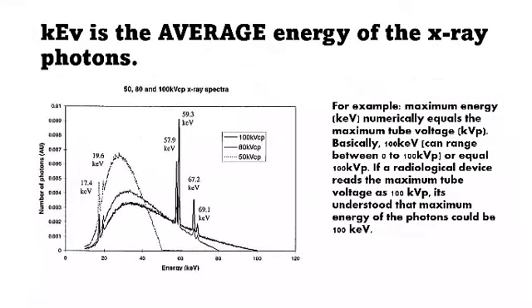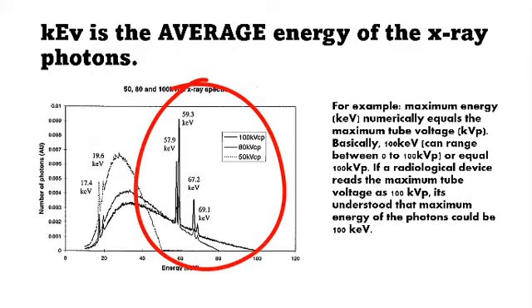As you adjust your kilovoltage in choosing technique, you must know the difference between keV and kVp. keV is the average energy of penetration of the beam, and kVp is kilovolts peak. It is the maximum. It cannot penetrate any more than that peak area. Usually the keV is about half or a little more than half of the kVp. So what we're saying is the average energy of a beam for 100 kVp would be about an average energy of 67.2 keV.